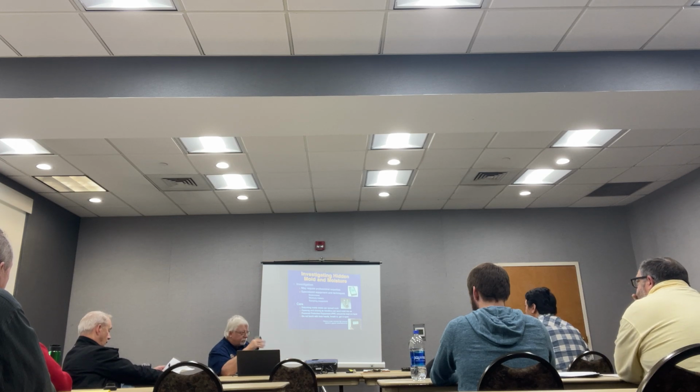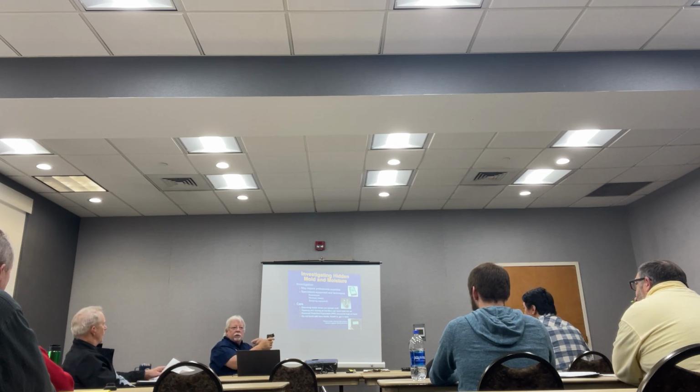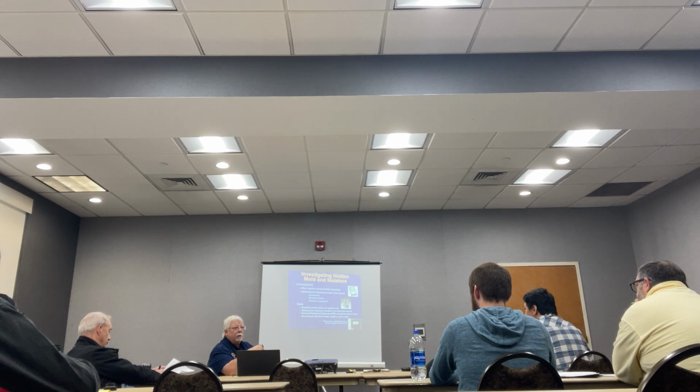So that's what this is for. It's just a quick, easy way. The other thing I use these for is if I wanna make sure, when I'm inspecting a house, that the heating and air conditioning works. I turn the heater on when I first go in there, and then I'll take a vent and shoot this, and it'll tell me what temperature it's blowing out. I'll know whether it's heating. Then I'll switch it to air conditioning and wait about 5 minutes so that it gets the warm air out. Then I'll shoot this at one of the vents, and it'll tell me what the air conditioning's blowing out at. So now I know if it's doing pretty good.